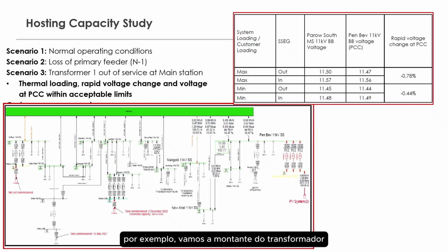And in this case, we also, for example, took one upstream main station transformer supplying this area out of service. And then we typically look at the thermal loading, the rapid voltage change, and the voltage at the point of common coupling at the substation where the generation sources are connected, and that's typically a table showing the variations. In this case, the customer was connected at what we call the PenBev substation. The Parow South is the upstream main station supplying that station, and there you can see the percentages of the rapid voltage change at the PCC, which is in this case, for example, within limits. The simulation diagram, as you can see at the bottom, also includes all the other SSEG or embedded generation systems in the network to obviously have a more holistic view of the impact.